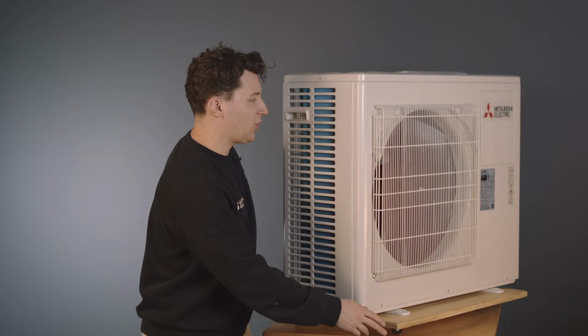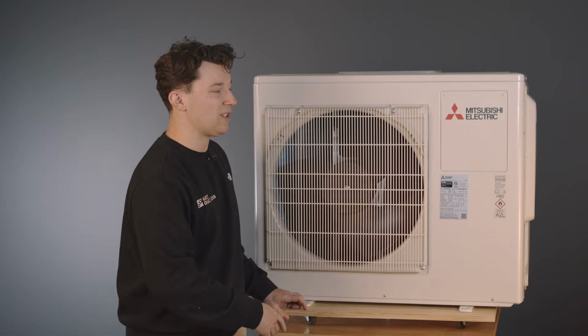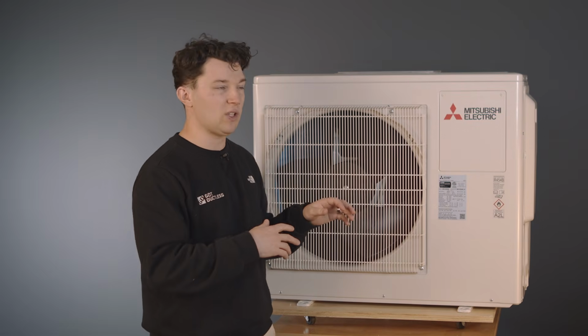But as a specification, as mentioned before, it's 2 zones, which means that you have to install 2 zones. It'll never be 1 zone empty, 1 zone complete. If you want to run it, you have to have both zones connected and running, per the rule that you have to have 2 indoor units connected to any multi-zone system at any given time if you want it to operate.